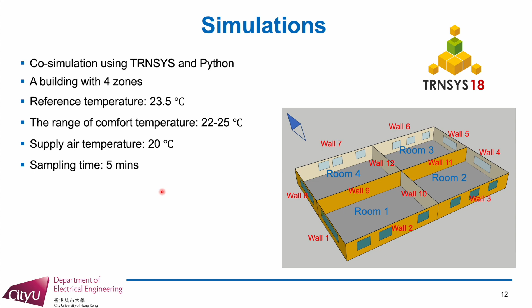We used two metrics to study the impact of different event triggering policies on the performance. The total violation for temperature is defined as the percentage of time instances where the temperature of at least one zone is outside the comfort temperature band. The maximum violation for temperature is defined as the value of the largest deviation of temperature from the comfort band among all zones and all time instances. We use the communication rate as a metric to study the impact of the optimal and threshold-based event triggering policies on the communication frequency between the system and the cloud.